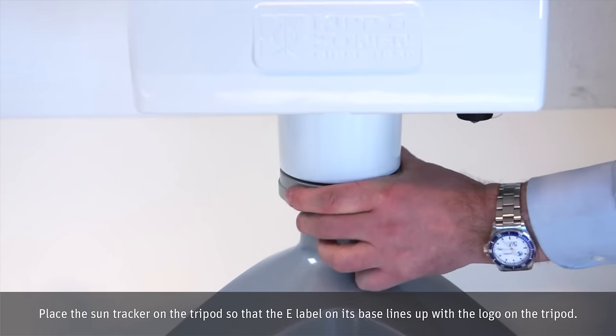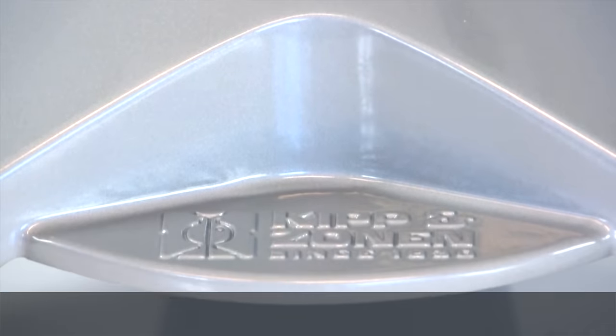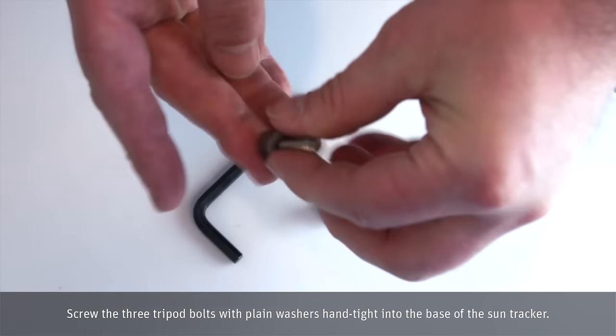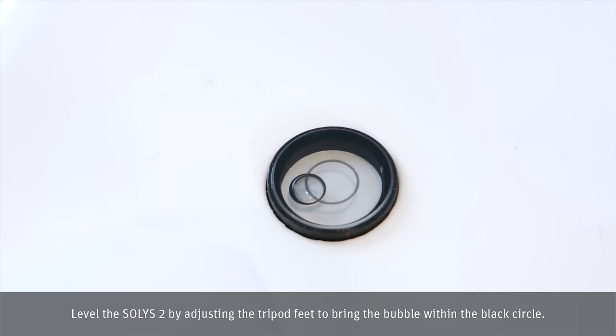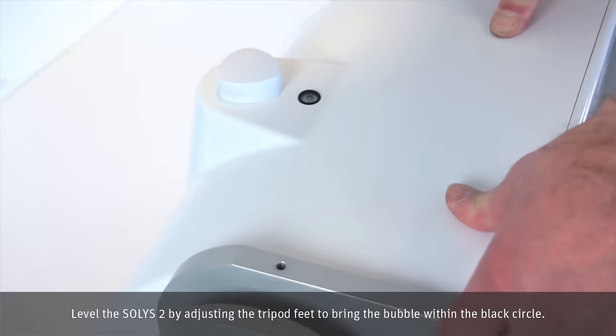Place the SunTracker on the tripod so that the e-label on its base lines up with the logo on the tripod. Screw the three tripod bolts with plain washers hand-tight into the base of the SunTracker. Level the SOLYS 2 by adjusting the tripod feet to bring the bubble within the black circle.